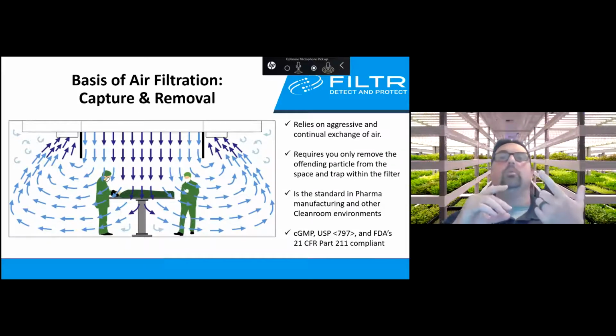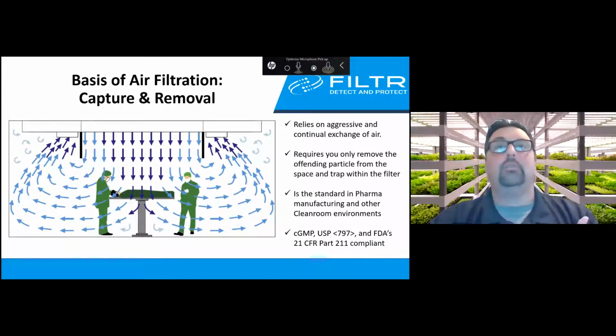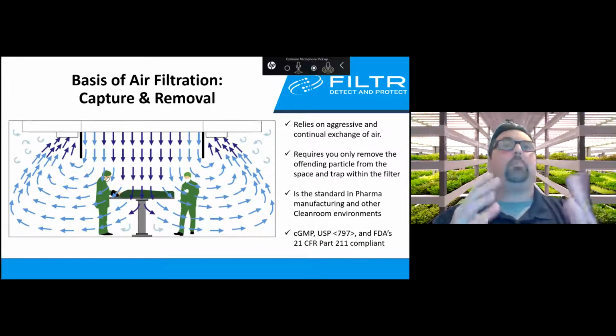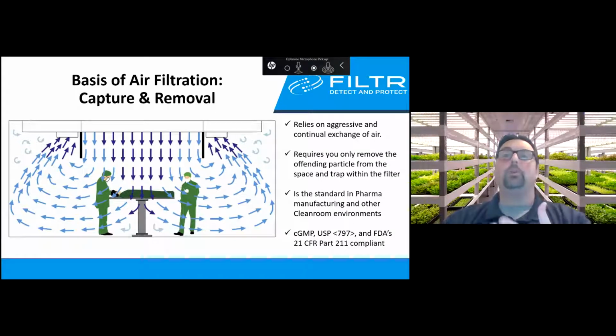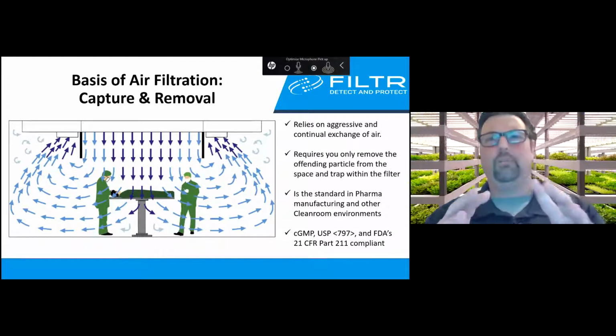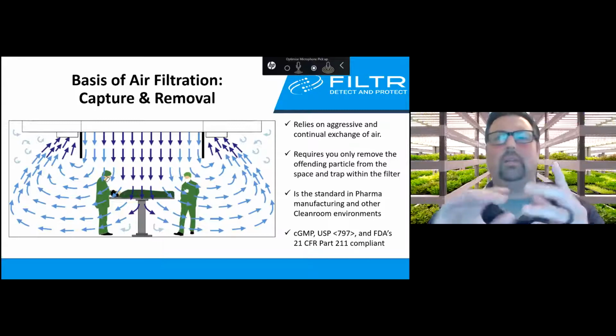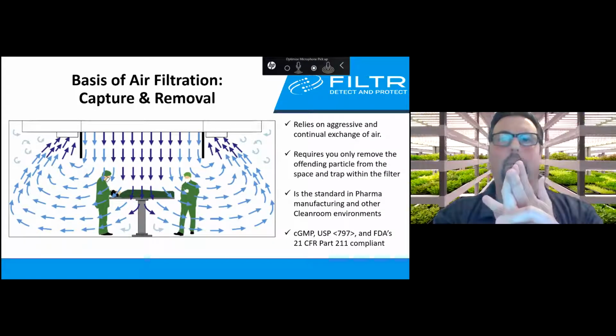So capture and removal relies on really aggressive, continual exchange of the air. It only requires removing the offending particle from the space and trapping it within the filter. This process is standard in pharmaceutical manufacturing and other clean room environments. This doesn't just apply to air filtration—it applies to your entire facility, from the way you build it to the way you operate it.